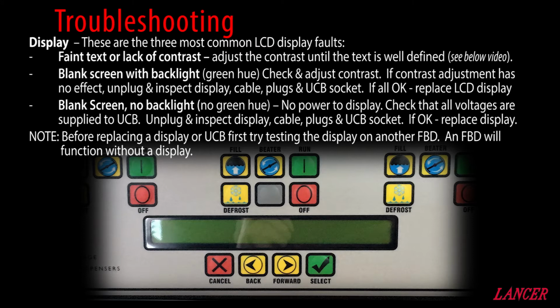Check that all the voltages are supplied to the upper control board, unplug and inspect the cables, plugs and sockets. If all okay, then replace the display. But before you do any of this, it's good to check the display on another FBD unit, because the FBD will work without a display.